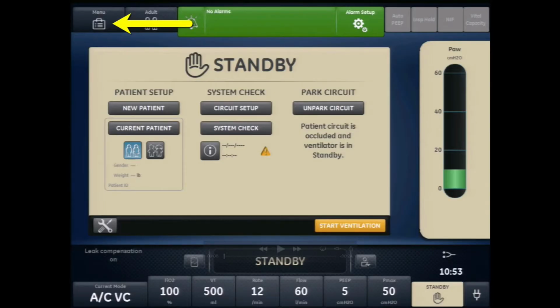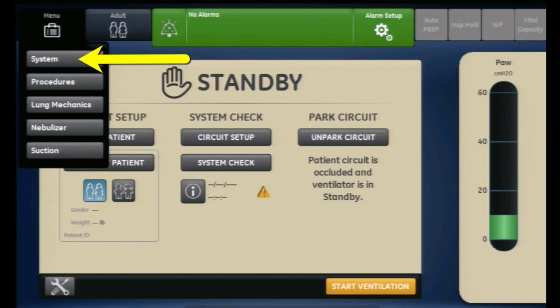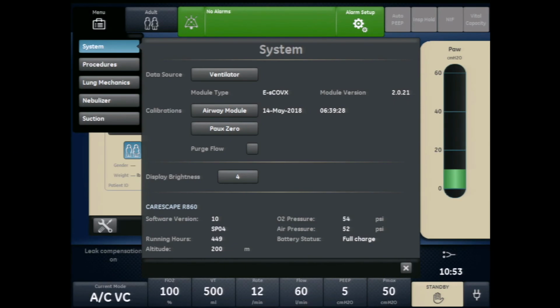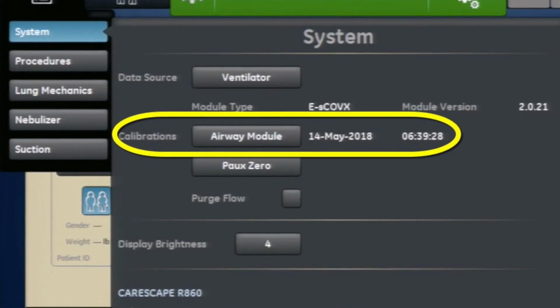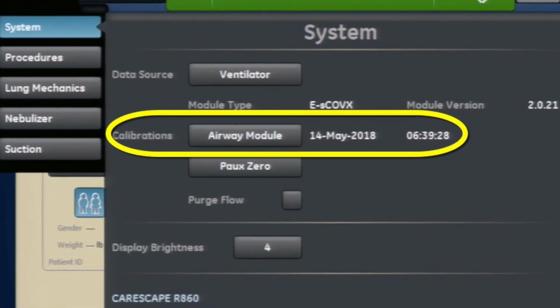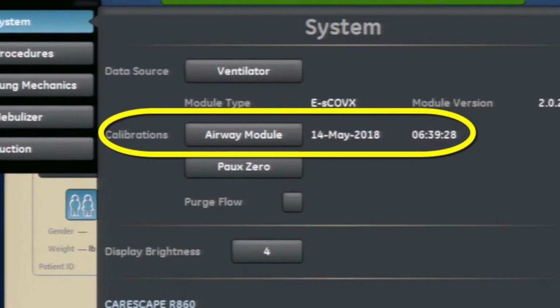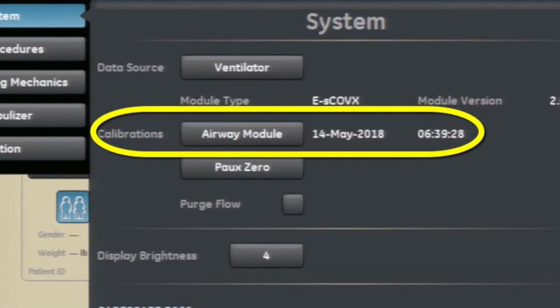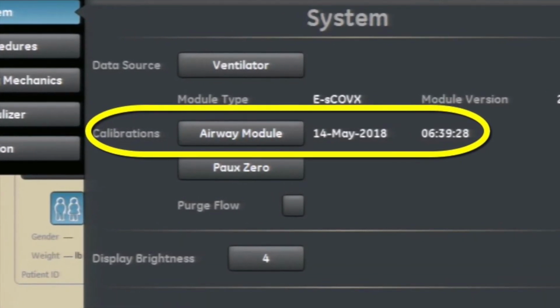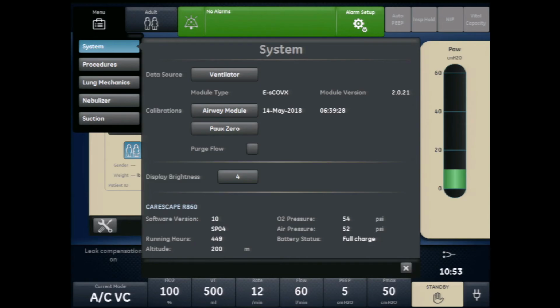From the standby screen, select the menu key on the top left-hand portion of the touch screen. Under Menu, select System. Under the Systems tab, you notice Calibrations. You have a choice between airway module and auxiliary pressure. When the airway module is in line, it will show the last date and time the airway module was calibrated. Select Airway Module next to Calibrations.